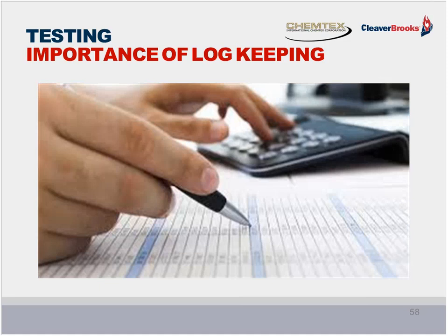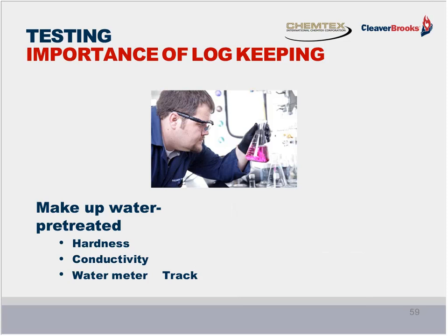I'd like to move on to something we've alluded to in the last section, and that's the importance of log keeping. And again, I'm not going to set specific limits for each facility, but I want to talk about what you should be testing and what your water treatment advisors should ask you to be testing for, depending upon the size of your plant. Are you testing your makeup water for hardness and conductivity, and are you tracking the makeup water going into the boiler?